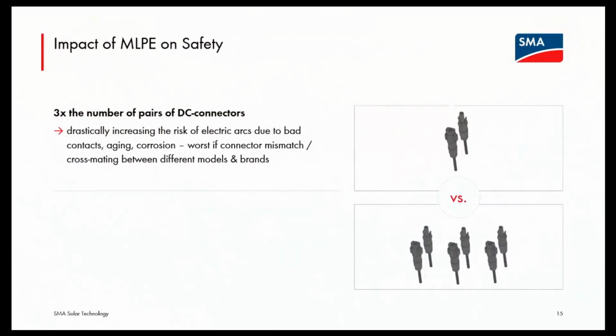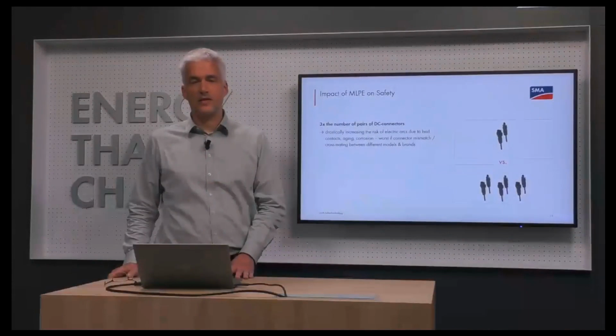Oh, there we go. Okay, so quick summary before I get to the environmental discussion. You've got 3 times the number of DC connectors, as I said. There is the risk of mismatch because the DC connectors which come with the PV module were attached to the PV module by the module manufacturer. Then you've got the manufacturer of the module-level electronics. They're adding their DC connectors. Ideally, they would be the same manufacturer, same module. Well, maybe they're not. Then it gets even worse, right? So you're increasing not just the number of connectors or connecting points, you're adding additional risk by potential mismatch between connectors. You get corrosion, and eventually corrosion leads to bad contact points, and eventually this might lead to sparks, to arcing, and to fire.